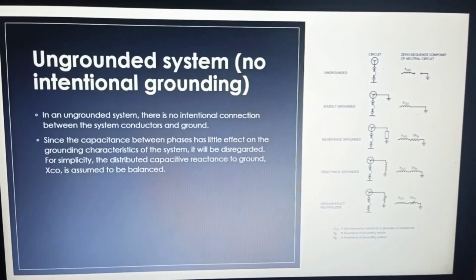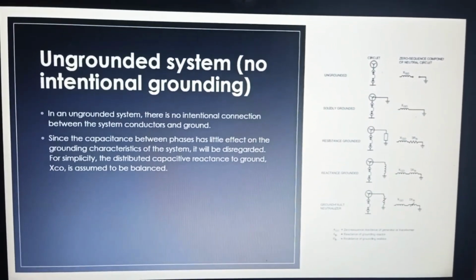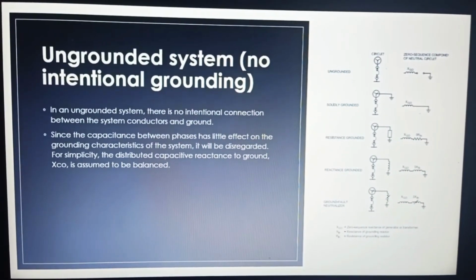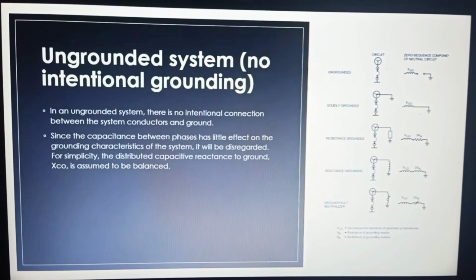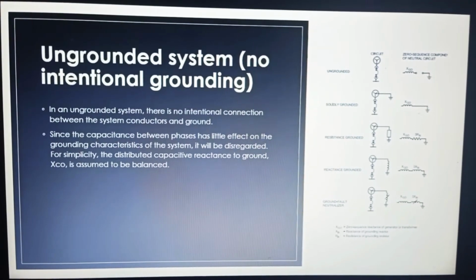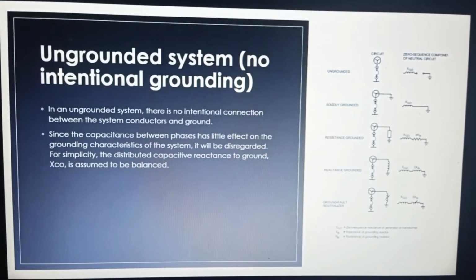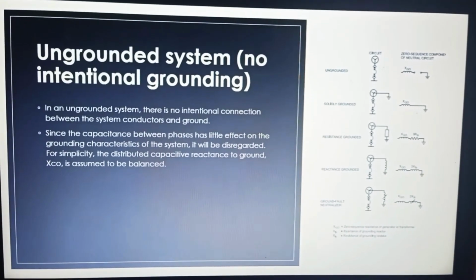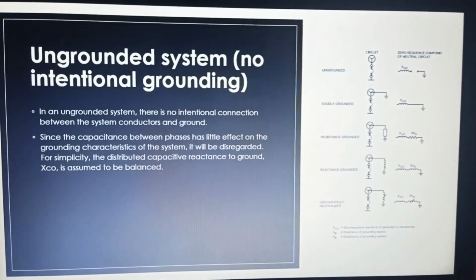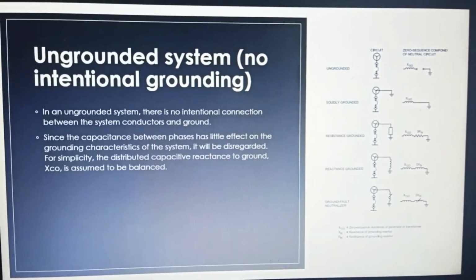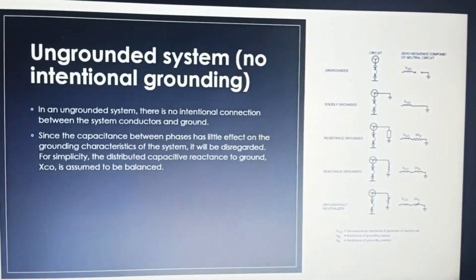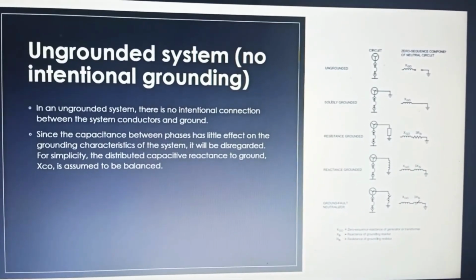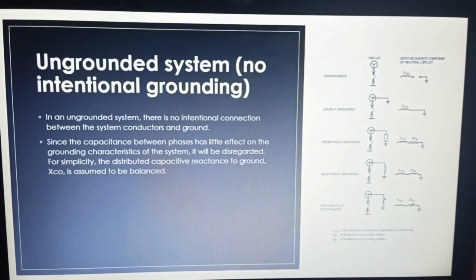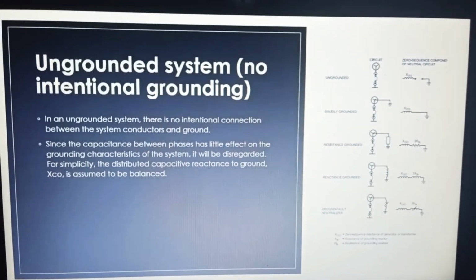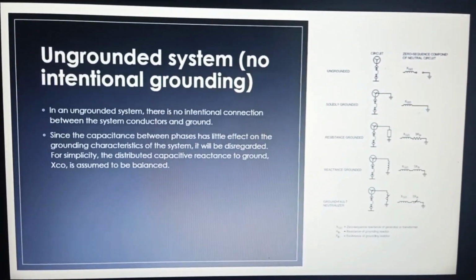The purpose of system grounding. System grounding is the intentional connection to ground of a phase or neutral conductor for the purpose of controlling the voltage with respect to earth or ground within predictable limits and providing for a flow of current that will allow detection of an unwanted connection between system conductor and ground. Such detection may then initiate operation of an automatic device to remove the source of voltage from this conductor.